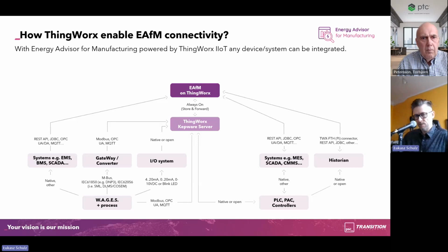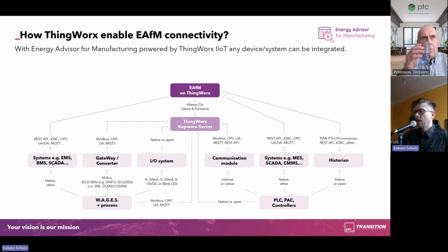If there are no such systems on site, we can speak directly to PLCs, PACs, to controllers with dedicated drivers, and Kepware is best at it. For Siemens, Rockwell, Mitsubishi, whatever you name it, they have it. In case the PLC does not have these functions enabled, we usually recommend our customers contact the provider of the machine. Usually it costs a little bit - enabling OPC-UA control requires updating firmware, or paying a small license fee, or adding a communication module, which will make this communication available.